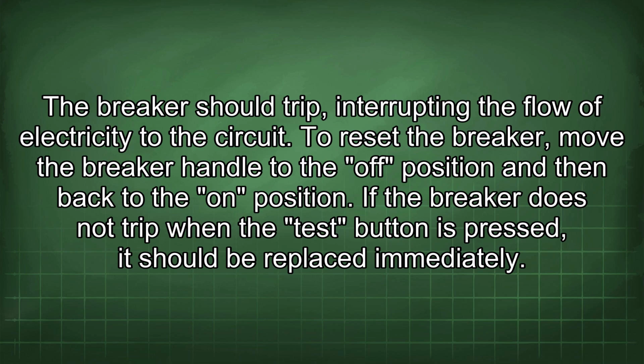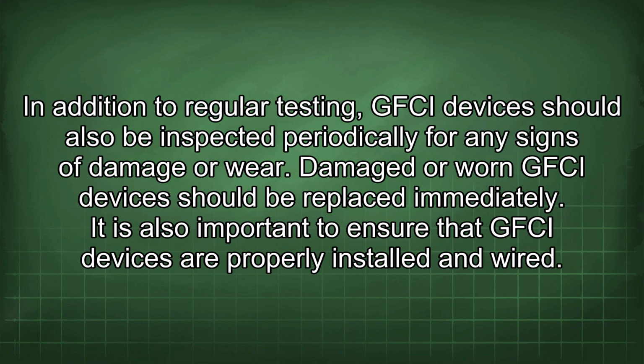To reset the breaker, move the breaker handle to the off position and then back to the on position. If the breaker does not trip when the test button is pressed, it should be replaced immediately. In addition to regular testing, GFCI devices should also be inspected periodically for any signs of damage or wear. Damaged or worn GFCI devices should be replaced immediately.